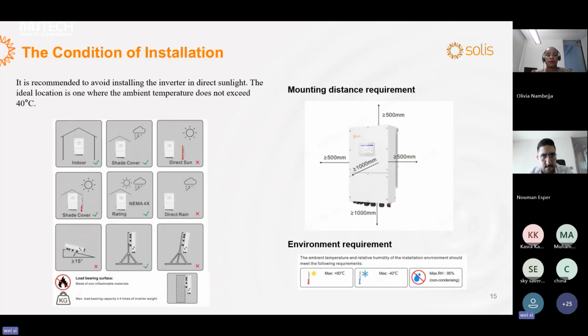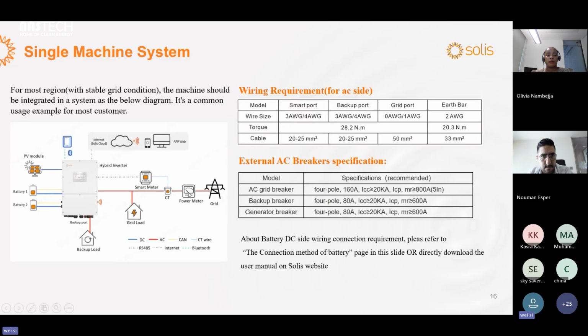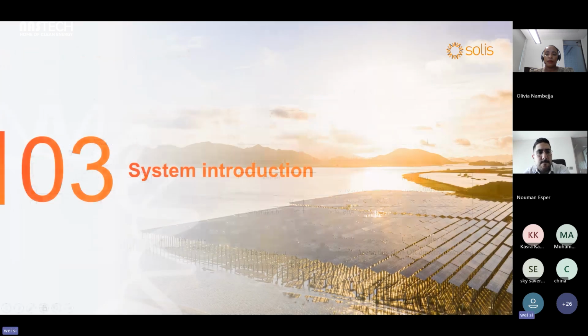You should follow the regulations for the installation. For the single machine system, you can connect two batteries, the backup load, the grid load, then the CT and the meter, as a single energy storage system. This table is about the wiring requirements and the AC breaker specification. You can take it as a reference during installation.